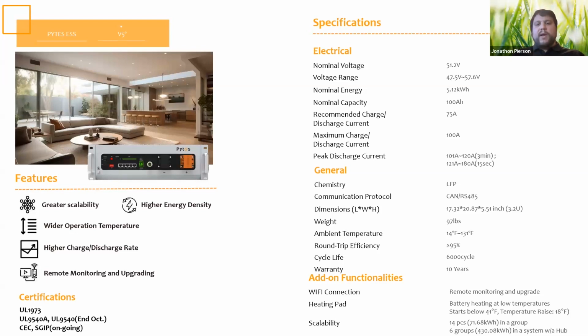Other than that, we have the very same footprint, other than the actual size and weight of the battery is less, which is great—more energy density per unit. Another big call out here is that it has the same warranty. It has 6,000 cycles at 90% depth of discharge.